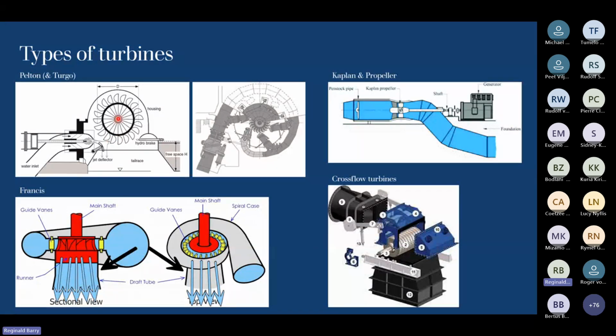And then on the bottom left, you've got a Francis turbine. So that's the runner in red that you see here. So you've got flow coming in radially and then passing through the turbine runner. And that turns the main shaft, and the main shaft turns the generator. So this is just a typical vertical Francis with a shaft in the vertical direction. You can also tip it on the side. You get vertical and horizontal Francis turbines.